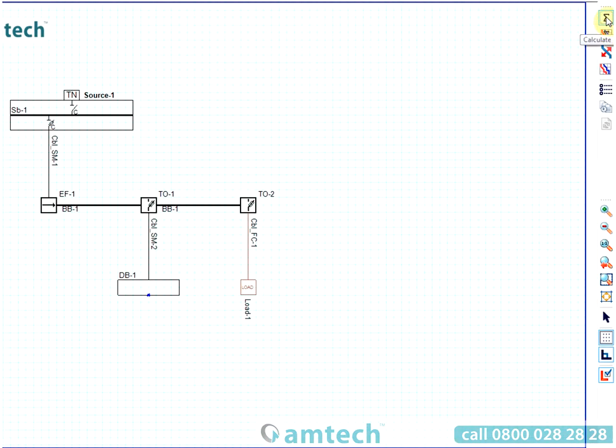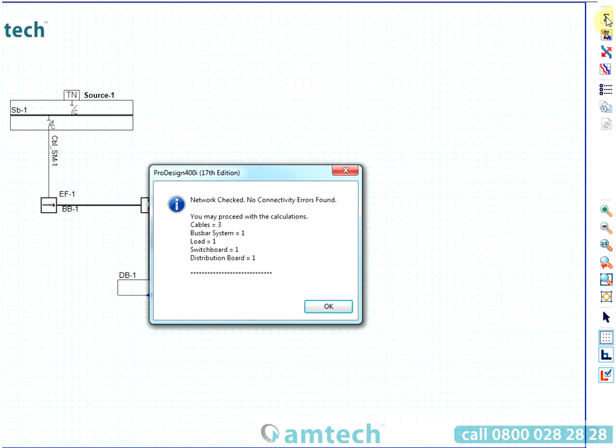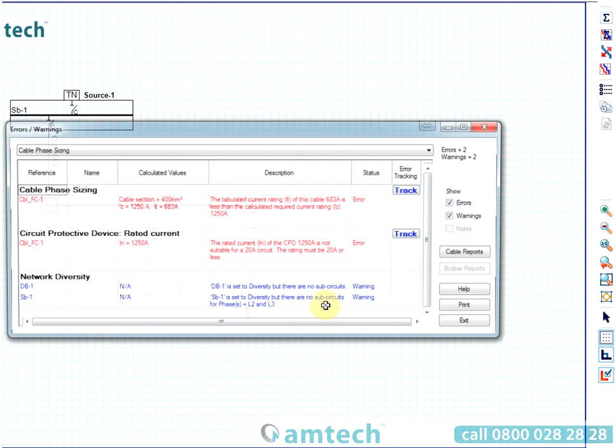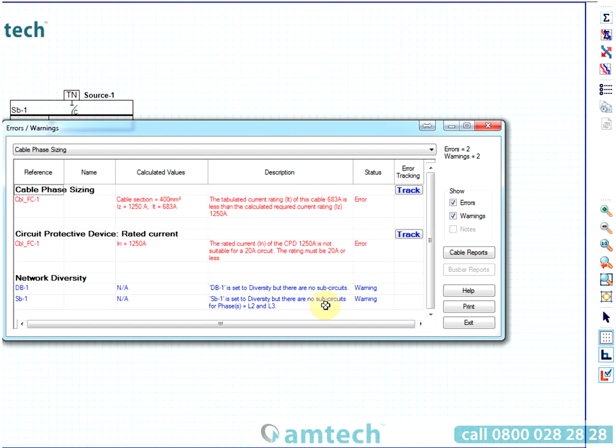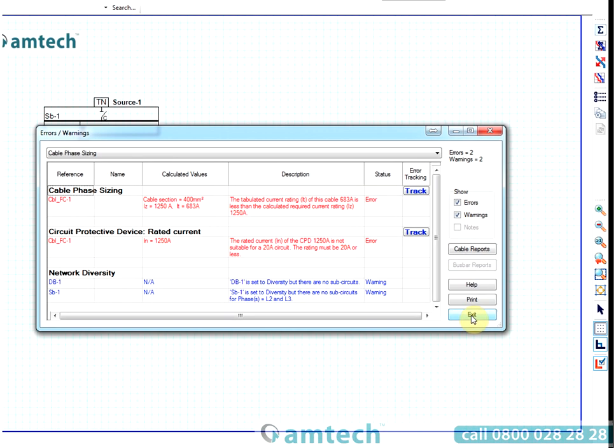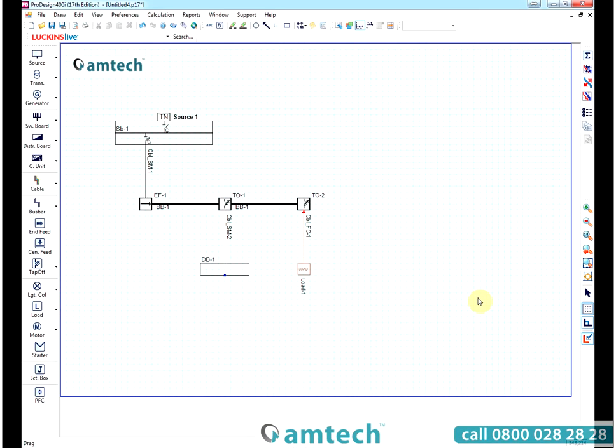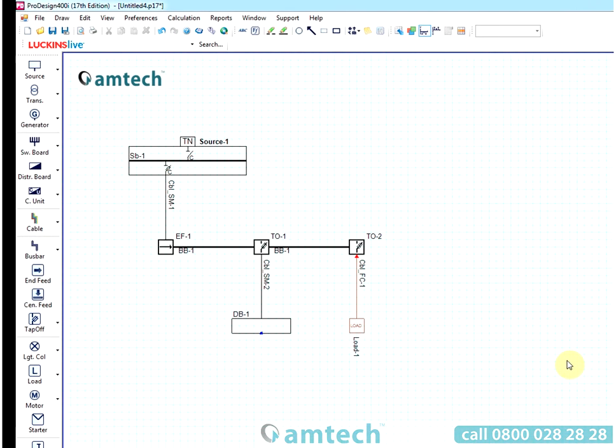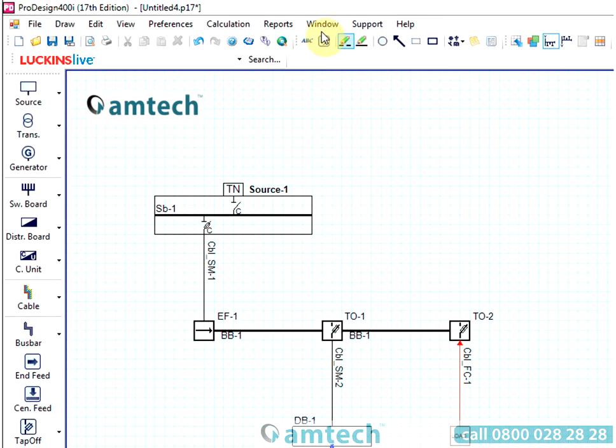When you click the calculate button, ProDesign quickly performs a wide range of calculations including protective device size rating, cable capacity requirement, line conductor adiabatic withstand, earth fault loop impedance check, earth fault disconnection check, phase fault level, protective device breaking capacity check, voltage drop, time current energy based discrimination check. ProDesign includes a large range of report formats.